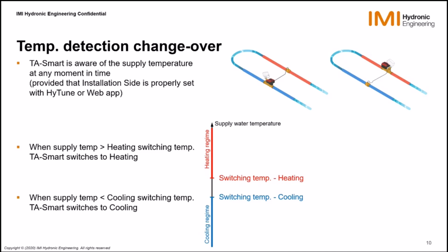Reciprocally, when the supply temperature is colder than the cooling switching temperature, then the TA-Smart switches to cooling and therefore assigns the max flow that has been defined for cooling. If the TA-Smart had its supply temperature, for instance, at 6 degrees below the switching temperature of 19 degrees, it is in cooling, and then you stop the installation, you shut the valve. So the water, including the supply water, starts to warm up. And maybe at a certain time, this water on the supply here will become larger than the switching temperature.